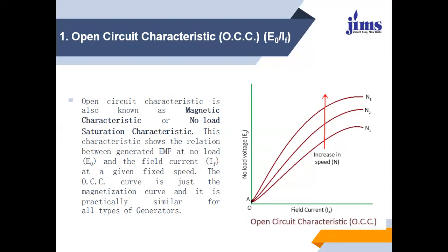As you will find here, on the y-axis we are taking the no load voltage, and on the x-axis we are taking the field current. It does not start from zero, it starts just above zero on the y-axis. Whenever we start the generator, we find that there is some EMF already built up over the generator. That causes the generated EMF of the machine.